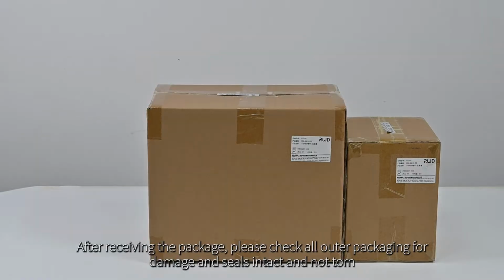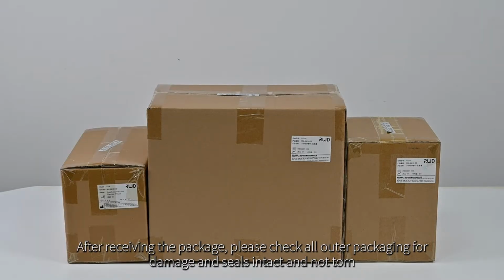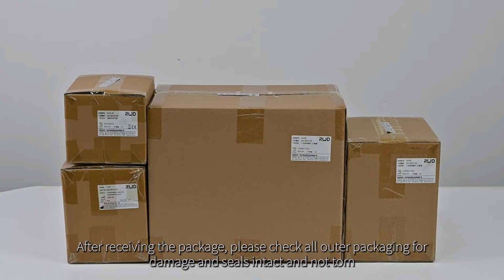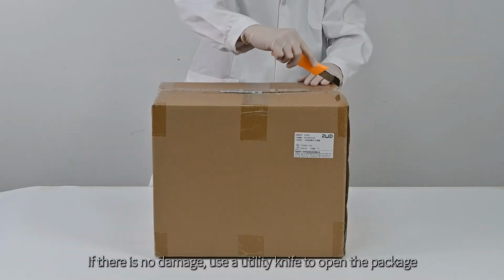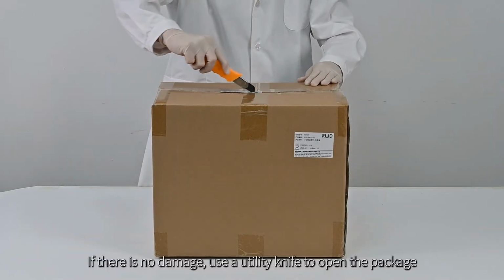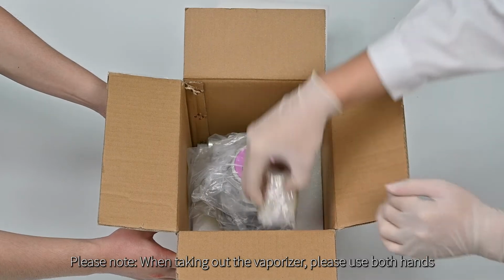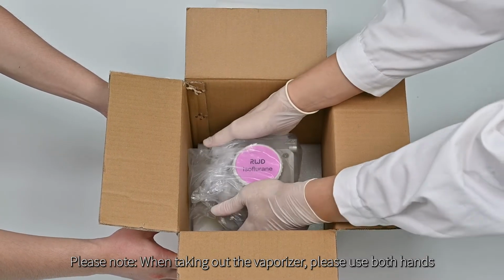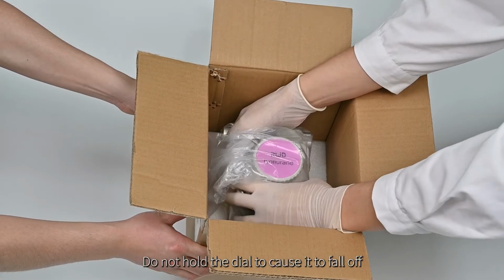First, anesthesia machine and accessories display. After receiving the package, please check all outer packaging for damage and seals intact and not torn. If there is no damage, use a utility knife to open the package. Please note, when taking out the vaporizer, please use both hands. Do not hold the dial to cause it to fall off.